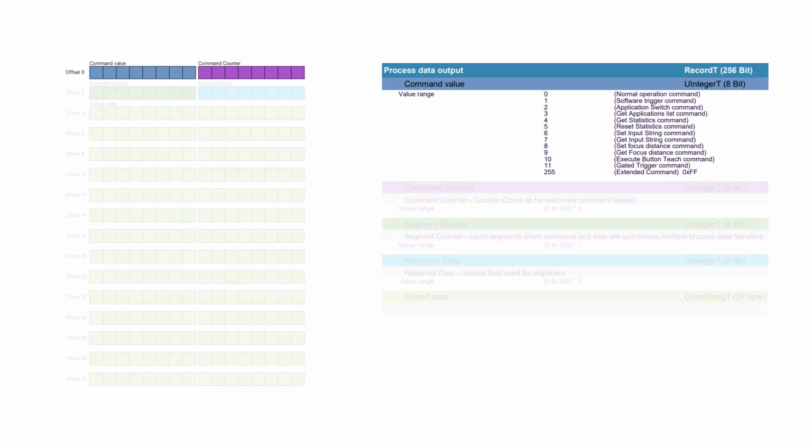This is done via the IO-Link output data. Here's the data structure found in the documentation. Let's simplify this further. For a general application, this 1 byte of IO-Link output data is all that is needed to trigger the O2I4. When this byte is changed to a 1, it triggers the camera.